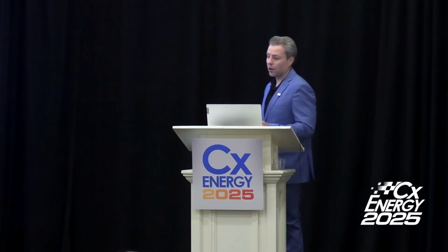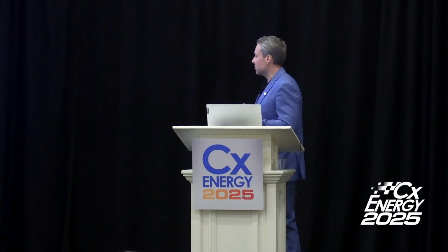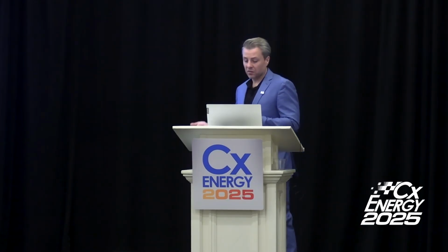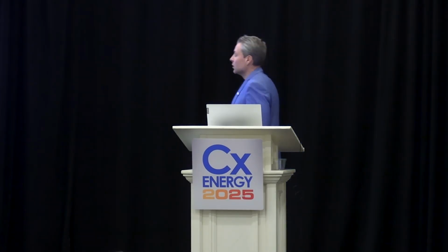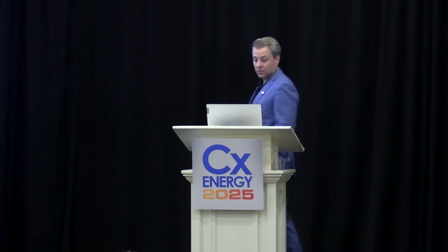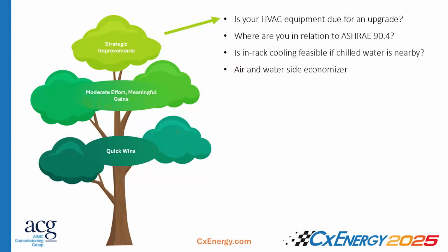Power infrastructure losses. So PDUs and UPSs have really been improving quicker than our HVAC equipment has. So a lot of the new PDUs and UPSs have eco modes where they consume next to no power. So that's also something, if you got a UPS from 1999 and you upgrade to a UPS from 2024, it is a capital investment, but there's been a lot of improvement in the technology for electrical consuming equipment in the last 25 years.